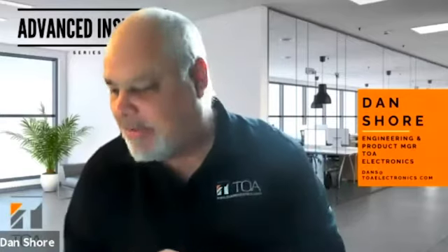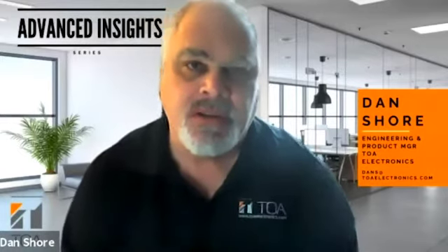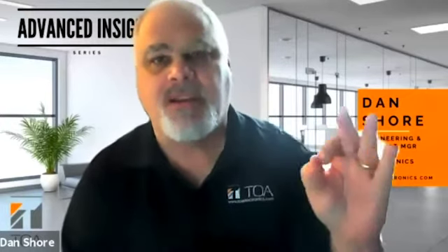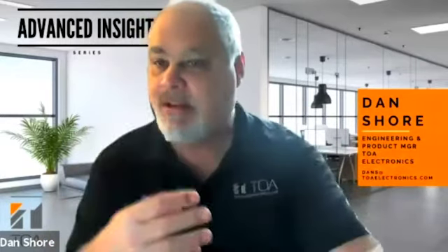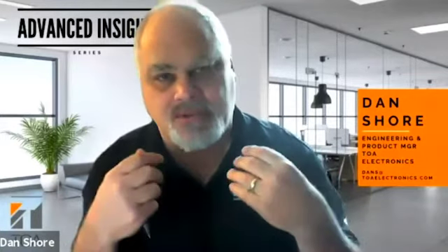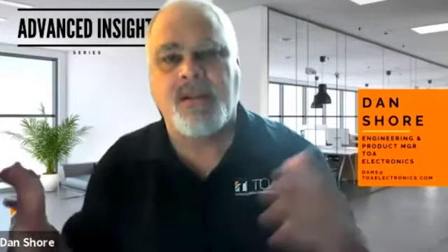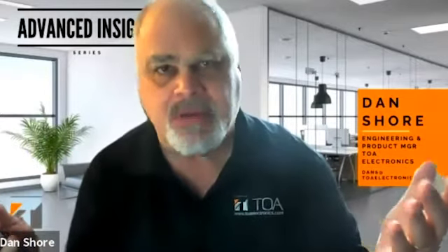The VM-3000 also supervises all of the speaker lines to NFPA 72, UL2572, and UL864 for you code guys out there. So per speaker line, it will tell you if there's a variance in the speaker impedance, if you have a number of speakers drop off the line. All of the control mechanisms are surveilled so that if there's an interruption in any of these circuits, a trouble on the fire alarm system, a trouble on the VM-3000, both systems can interact and let the building management know what's going on.